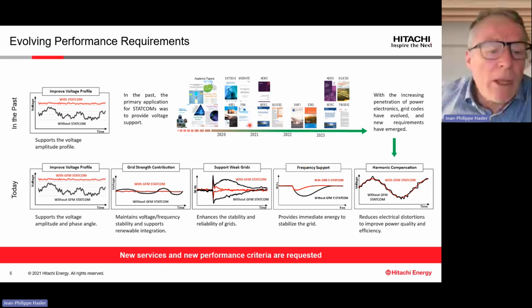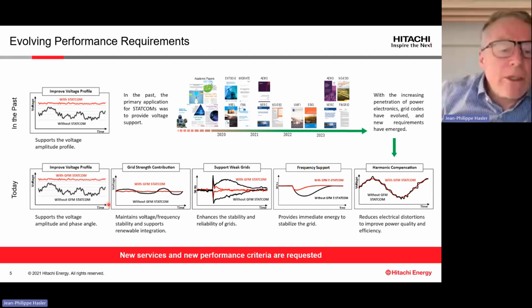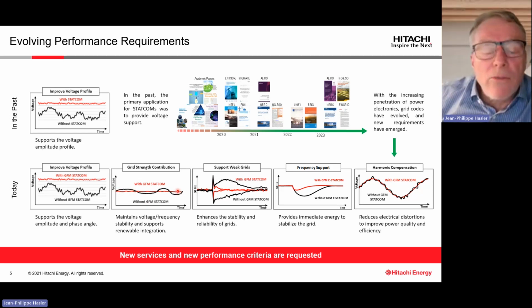FinGrid or many TSOs, they say what we have to do for a STATCOM is, first, what we have been doing in the past, which is to maintain the voltage profile. That means to get a stable voltage. We have to contribute to the grid strength, which means that if any type of converter starts to inject some fluctuating power or reactive power, that should not result in a big deviation in the voltage or in the frequency.